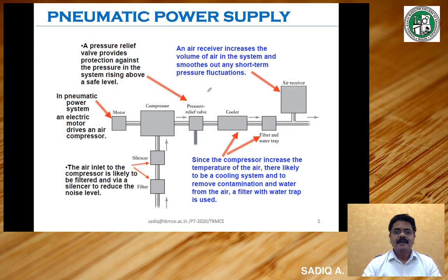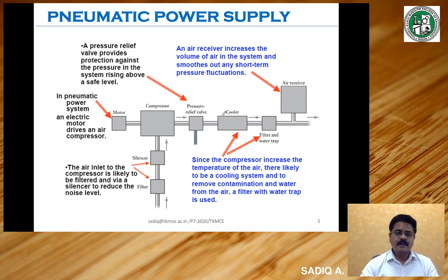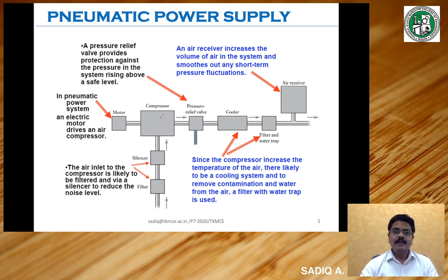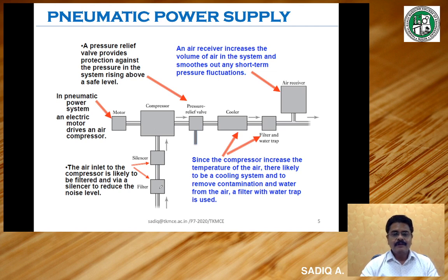Let us see the pneumatic power supply. It is meant for providing regulated pneumatic power to the external circuit. This consists of a filter, a silencer, a compressor driven by a motor, a pressure relief valve, a cooler, a filter and water trap, and an air receiver. When compared with the hydraulic power supply, instead of a pump we use a compressor because in a pneumatic circuit we use compressed air or gas for actuation. Compressed air is developed by means of a compressor. There is a filter to filter out any dust or particles entering the system.